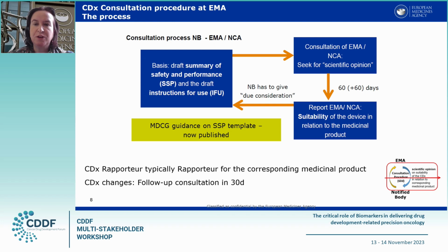So the notified body, before issuing an EU technical documentation assessment certificate for the companion diagnostic, and on the basis of the draft summary of safety and performance and the draft instructions for use, shall consult one of the competent authorities regarding the suitability of the device. This new consultation with the agency focuses on the suitability in relation to a medicinal product, and therefore this is a small part of the big puzzle that is the conformity assessment.